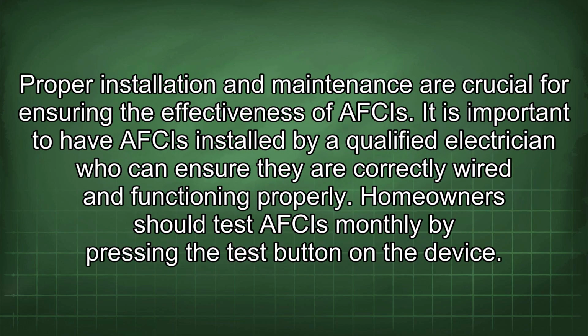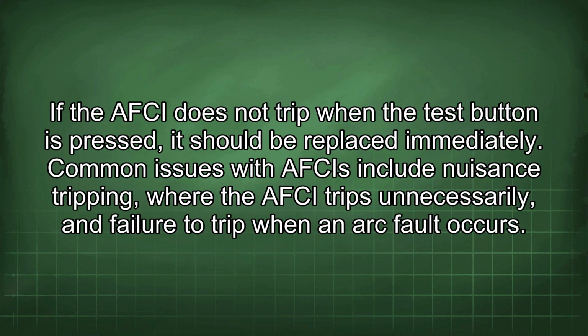Proper installation and maintenance are crucial for ensuring the effectiveness of AFCIs. It is important to have AFCIs installed by a qualified electrician who can ensure they are correctly wired and functioning properly. Homeowners should test AFCIs monthly by pressing the test button on the device. If the AFCI does not trip when the test button is pressed, it should be replaced immediately.